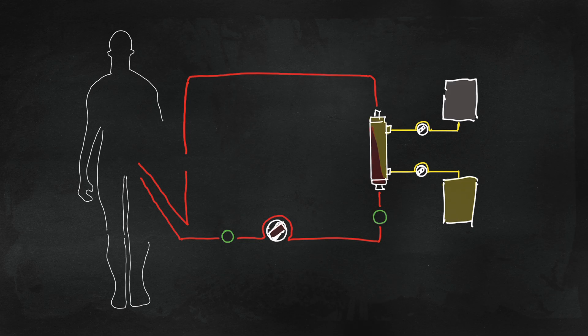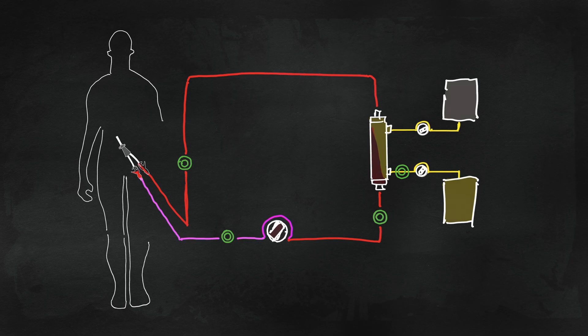Dialysis circuits will have pressure sensors to monitor circuit hemodynamics. On the bloodline, pressures are negative before the blood pump and positive after.